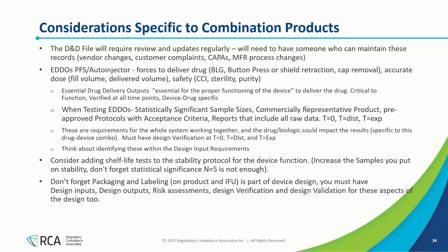And don't forget packaging and labeling. So when it comes to medical devices, packaging and labeling is considered part of the device design. You have to have inputs and outputs and your risk assessment and verification and validation for the packaging and labeling as well. This includes the package insert or prescribing information where you have your instructions. It also includes the on-product labeling. If there's printed cartons, if there's a sticker on the device itself, all of that requires design controls around it.